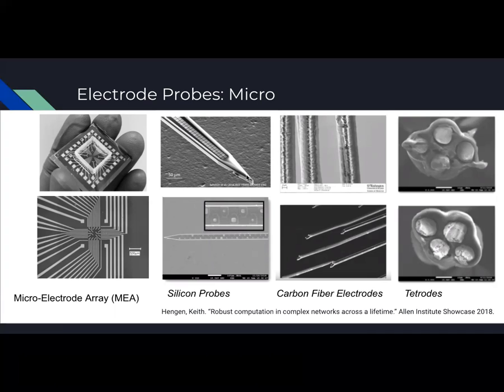So when you're inserting these probes, if they're really thick, you might actually pierce and puncture neurons. And also when a probe damages the brain, you have other supportive cells that are there to nurture and protect the brain coat these electrodes so that they insulate them and you're not able to record properly. So basically they're trying to reject the implant, and because there are so many supportive cells around the area, they will insulate and stop any kind of useful signal recording. So having small and flexible electrodes is important, to not have that kind of effect.